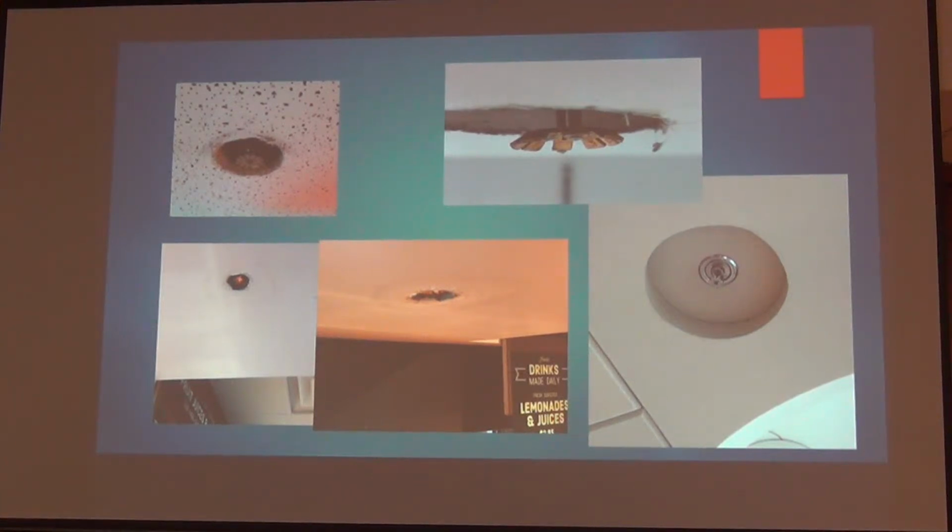Just a heads up, if no one's seen it, there's a new decorative craze going around, taking ceiling tiles out, leaving the grid in. Particularly a couple of hair salons that we saw recently. There's no mechanical permit often, the ducts aren't changing. So you're not out there, but usually the electricians are. Let the electrical inspector know if you see something like that. We just changed the ceiling height. You've got pendants hanging down to the level of the grid, and now suddenly you've got 2 feet or more over the top of this thing, which will delay the activation of those sprinklers.